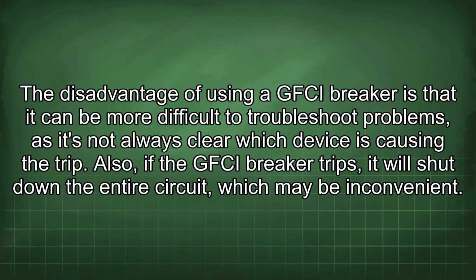The disadvantage of using a GFCI breaker is that it can be more difficult to troubleshoot problems, as it's not always clear which device is causing the trip. Also, if the GFCI breaker trips, it will shut down the entire circuit, which may be inconvenient.